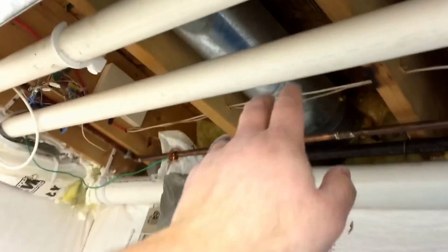Also you can see there are pipe hangers to hold the pipe up. They should be every 5 feet or so. You can see one down there, and then I have one here. On this one, we got a joist here, and I don't think we did it there because of all the phone line there, so we put a hanger here. But that's the whole thing, to hold this pipe and keep it pitched, because when these furnaces run, they create condensation, so you want the condensation to run back to the furnace and drain out. So many times I get calls in the wintertime where these pipes aren't hung correctly and they sag and the water sits in there and wreaks havoc, a whole ton of issues.